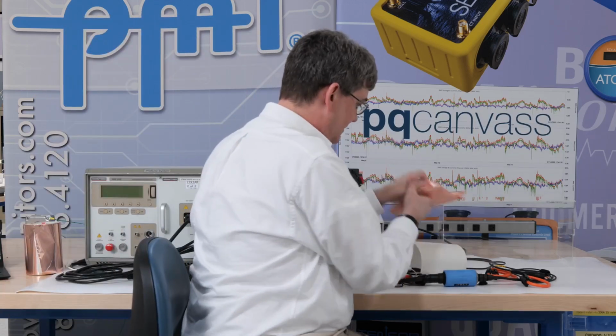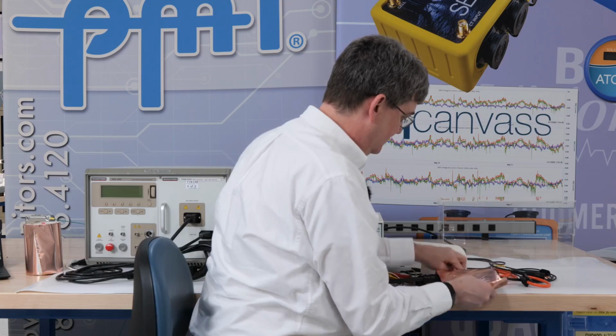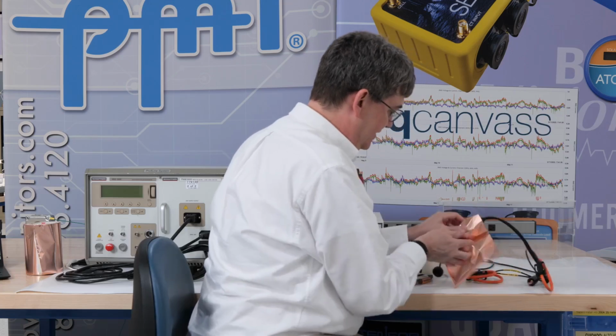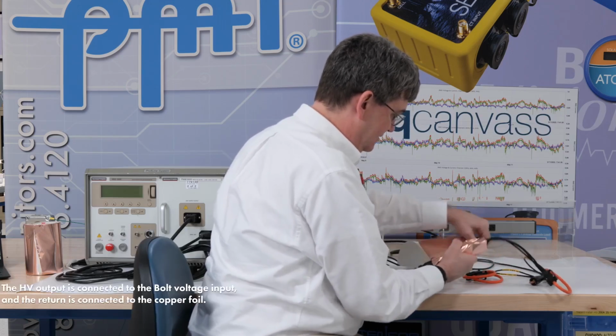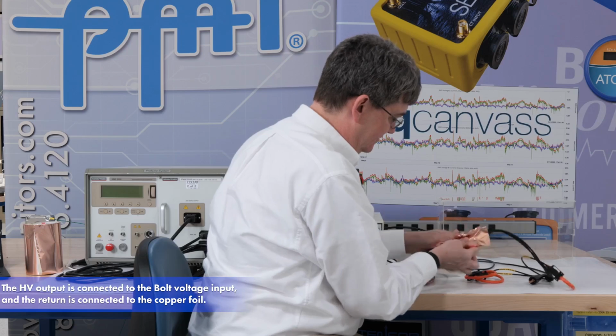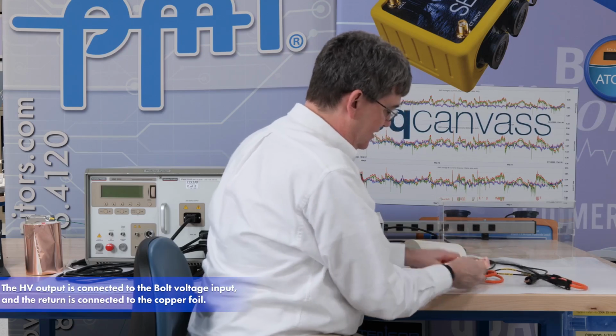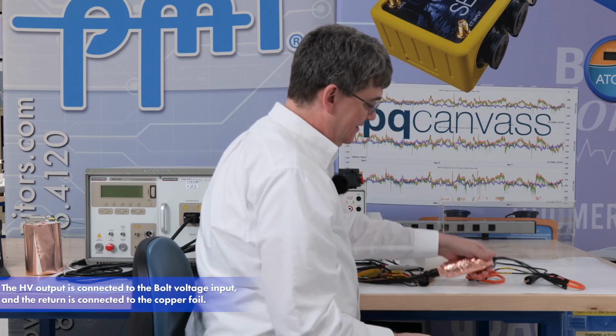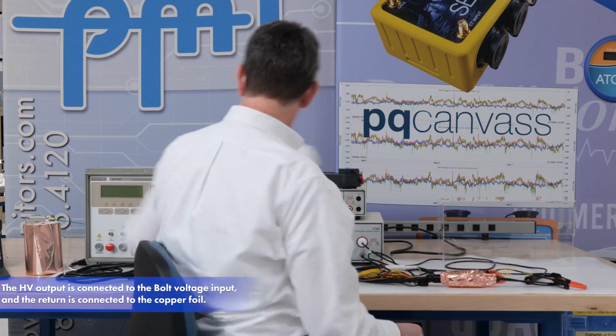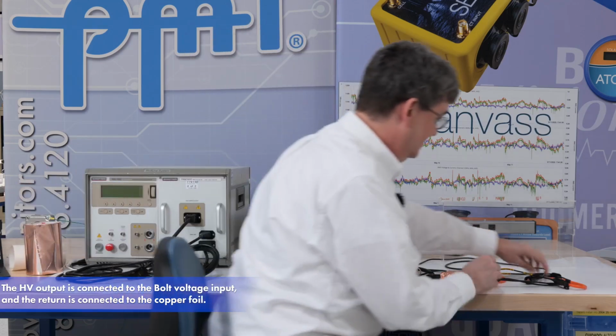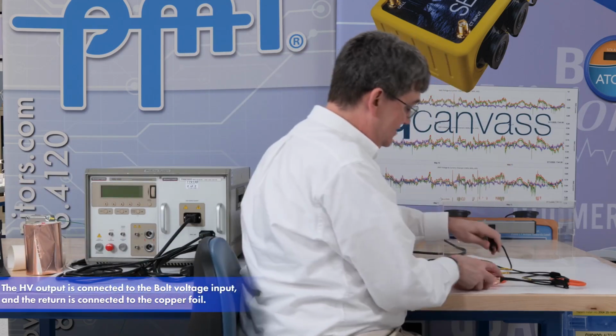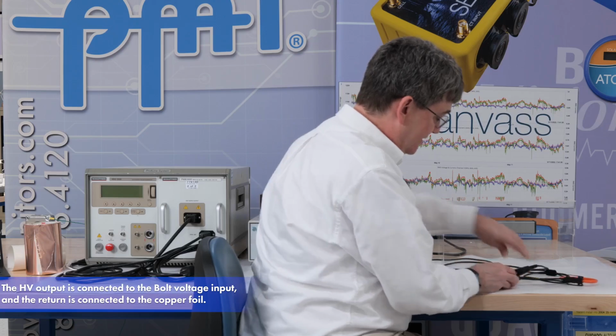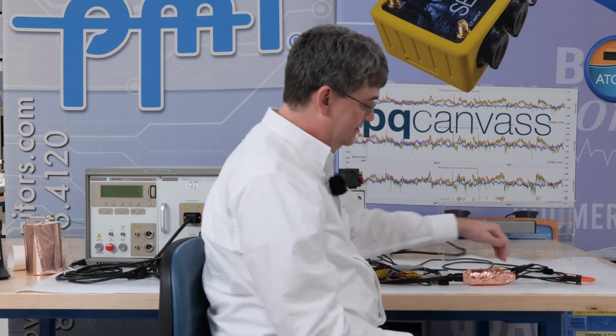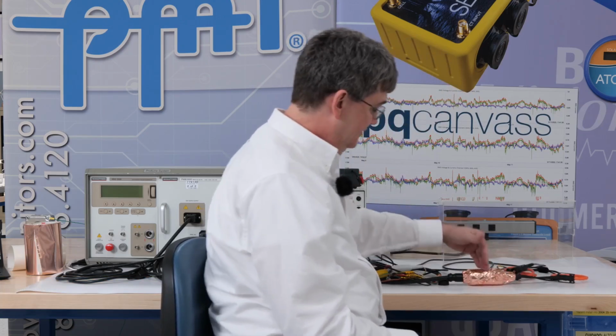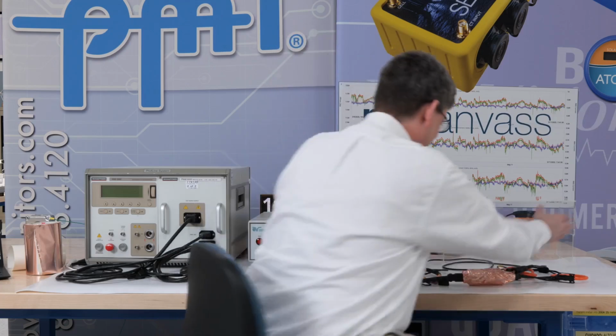So take this copper sheet, wrap it around the bolt tightly, and this simulates a person's hand that might be gripping the bolt while an impulsive transient occurs. So we're going to take the return of the Hipot tester and actually connect it directly to the copper foil to see if there are any hidden creepage or clearance paths to the isolated side of the bolt.